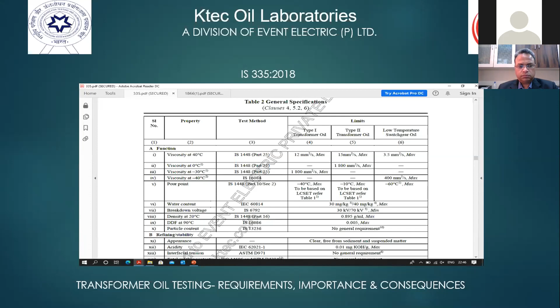On the right side are the requirements, the minimum and maximum values. In the case of breakdown voltage, two values are mentioned, 30 kV or 70 kV. 30 kV is for unfiltered oil. The minimum requirement is 30 kV. A new transformer oil should have a minimum breakdown voltage of 30 kV when unfiltered. When we have filtered the same oil, before using it in the transformer, it should have a minimum value of 70 kV after filtration. Like density at 20 degrees Celsius, the value is 0.895. That is the maximum. A minimum or maximum is mentioned after the parameters.